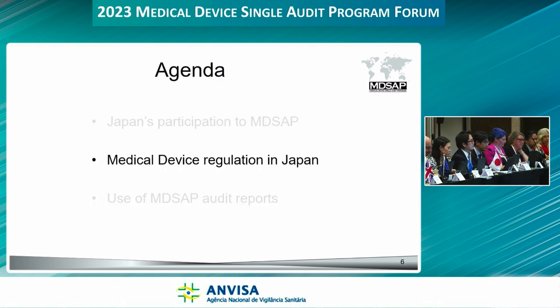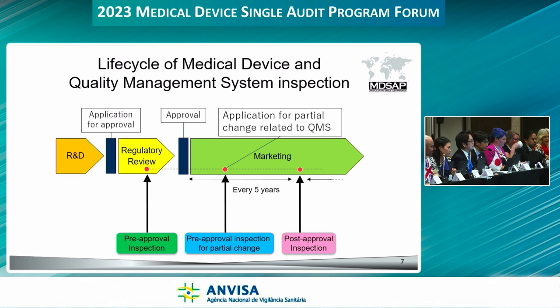Next, I will talk about Japan's medical device regulation. This slide shows a schematic representation of the regulations regarding market approval and QMS inspections for medical devices in Japan. In terms of QMS inspections, there are pre-approval inspections, inspections at the time of partial change of medical devices, and post-approval inspections. In Japan, MDSAP audit reports are accepted for these inspections, with some exceptions depending on the type of product and so forth.